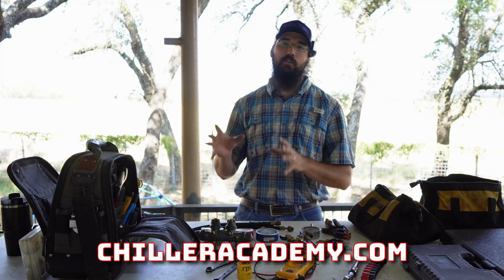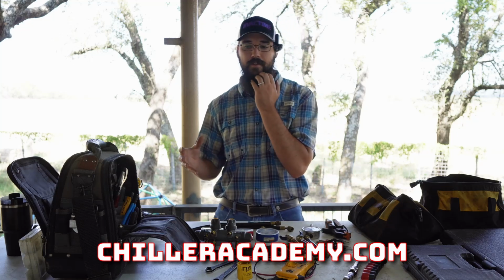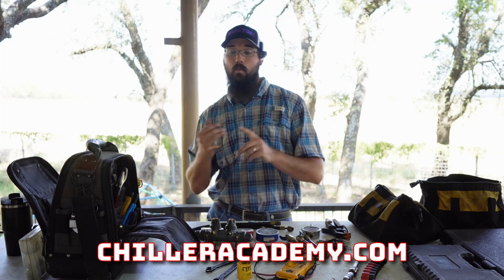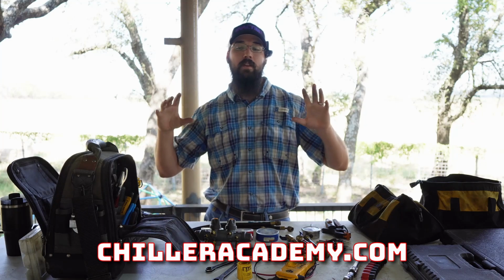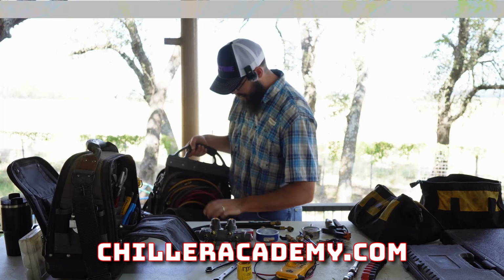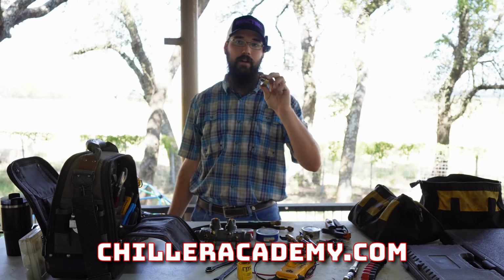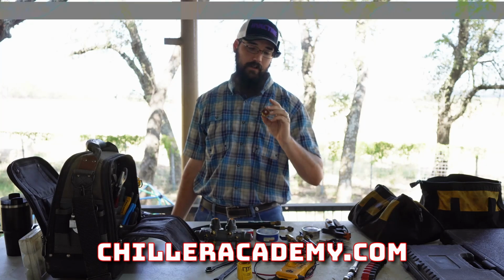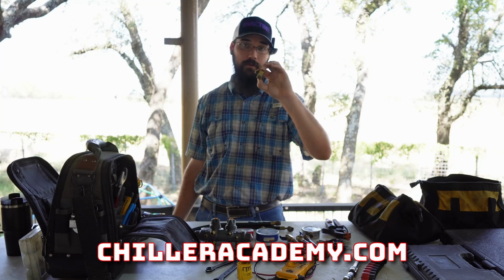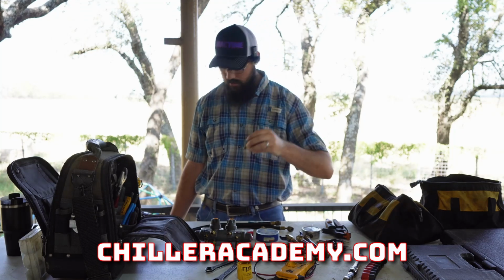A couple other small items are really specific to the chiller side stuff that I didn't really have to deal with when I wasn't working on chiller things. One, having tank adapters. The tanks we service and work on have much larger connections on them, and so they don't use a standard flare. Most of our hoses are using a flare connection. This is a tank adapter, so this is adapting down to a 1/4 inch. You can get these in 1/4, 3/8, 1/2 inch. I carry all those sizes.